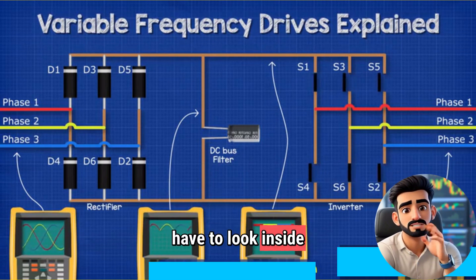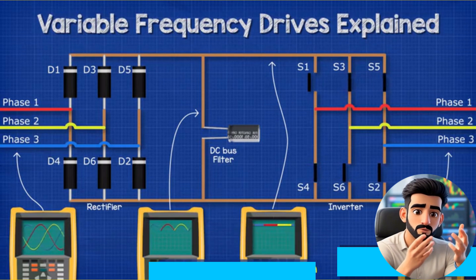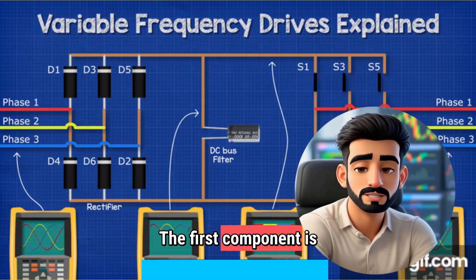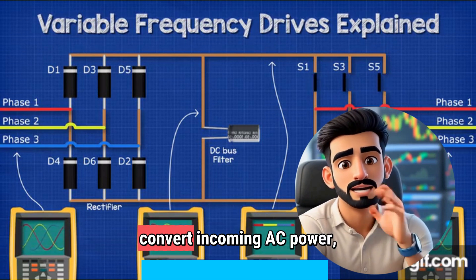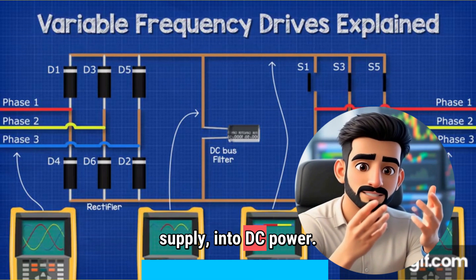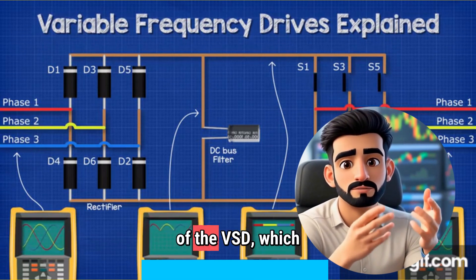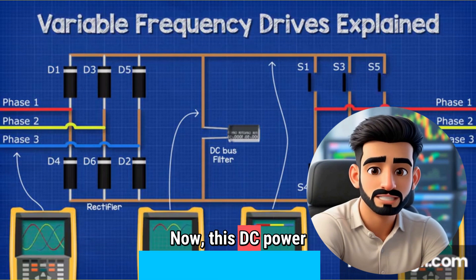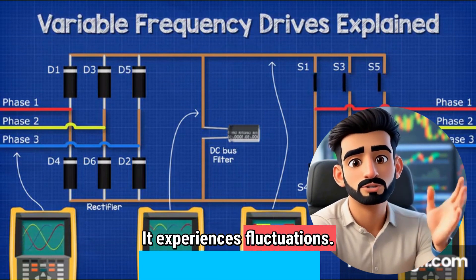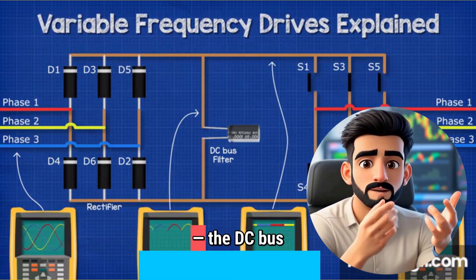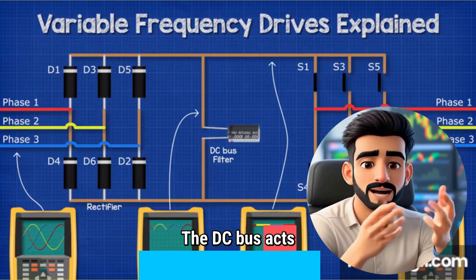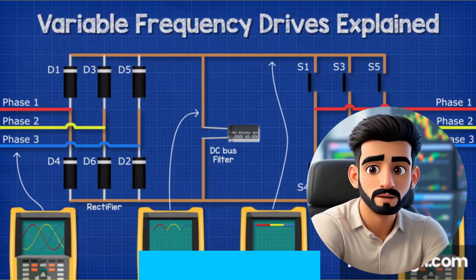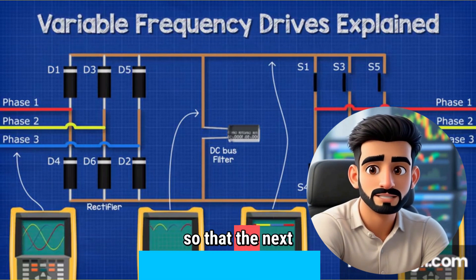A complete setup of a VSD consists of four main components. Understand these well, because they form the foundation of VSD's working. The first component is the rectifier. Its job is to convert incoming AC power — which comes from our supply — into DC power. You can think of it as the gatekeeper of the VSD, which takes AC power and converts it into DC. Now this DC power that is generated is somewhat unstable; it experiences fluctuations. Here, the role of another component comes in: the DC bus, or DC link. The DC bus acts like a reservoir — it stores the rectified DC power and filters it to produce a completely smooth and stable DC voltage, preparing a steady supply so that the next stage can operate properly.